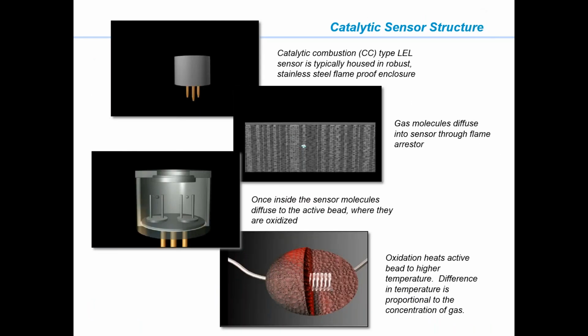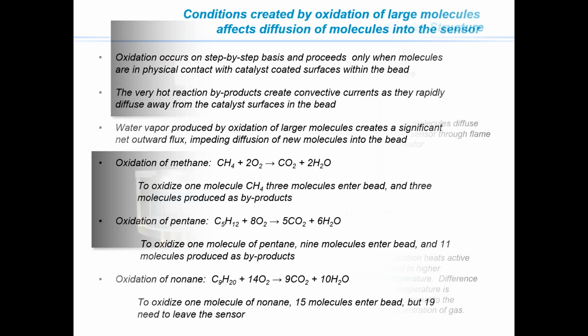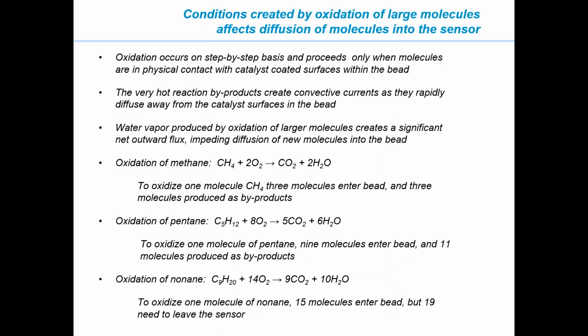What we do also acknowledge about the catalytic LEL sensor is the way that it detects gas is by oxidizing or burning the gas, and it includes internal components that limit the ability of the sensor to detect large hydrocarbon, large VOC molecules in the LEL range. If you wonder why a standard LEL sensor has such a hard time detecting diesel vapor, it's because the size of the molecules are large.